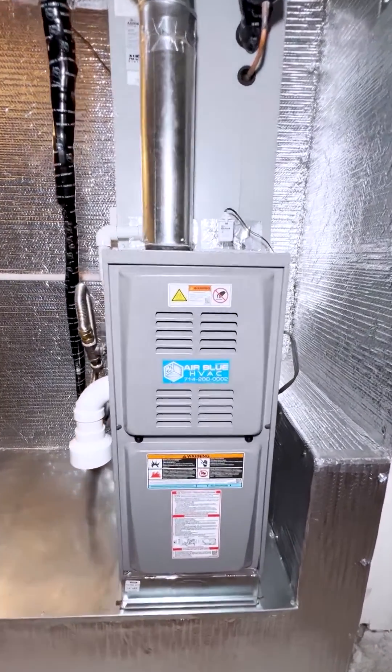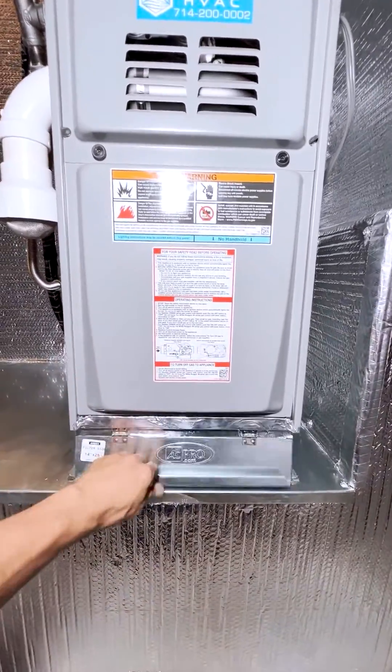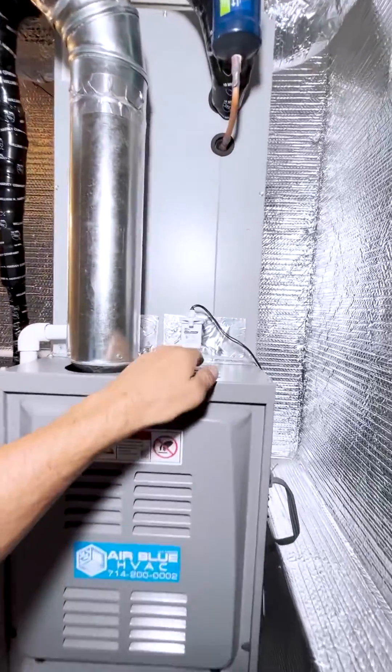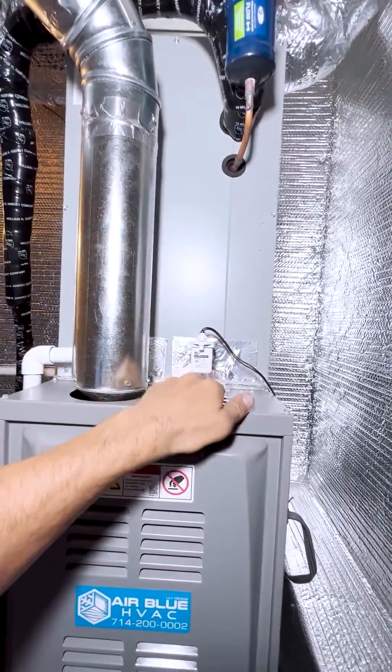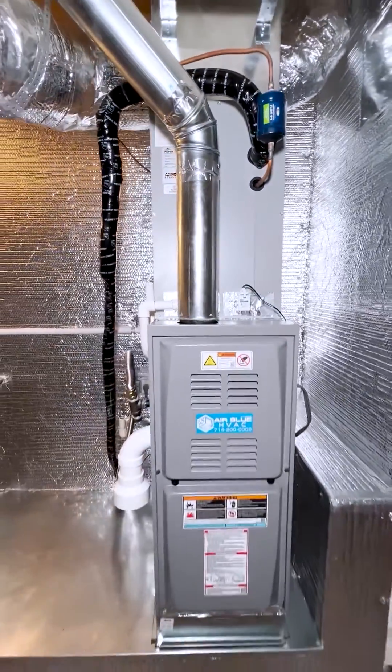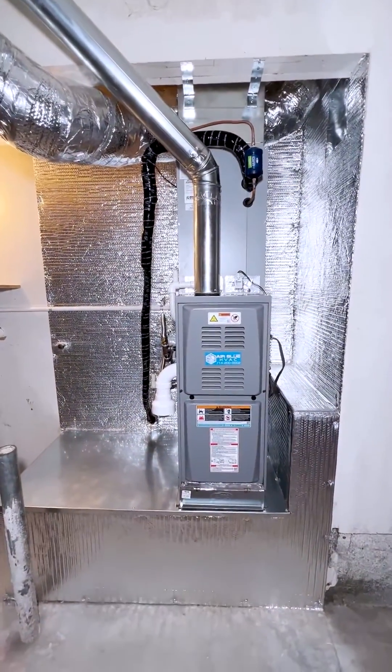This gas furnace is matched with a filter box that takes two-inch air filters, a new evaporator coil, a new water sensor on the secondary drain line, and a refrigerant filter dryer. The return cavity is fully sealed.